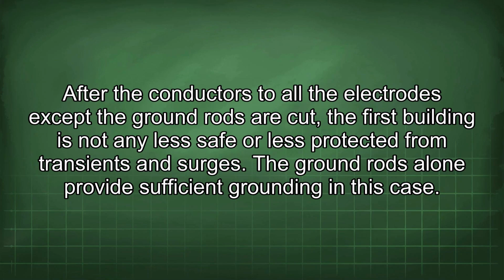After the conductors to all the electrodes except the ground rods are cut, the first building is not any less safe or less protected from transients and surges. The ground rods alone provide sufficient grounding in this case.